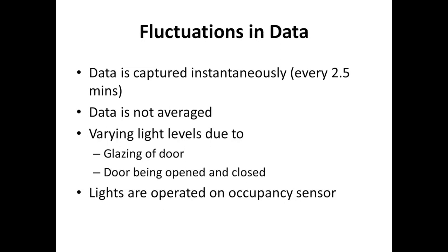To show you another example where we used the same sensor, we also installed these in the corridor of the same building. In this building, the corridor did have windows and doors with glass on them. These light sensors in the hallway picked up lighting other than the overhead lights that we were trying to monitor.